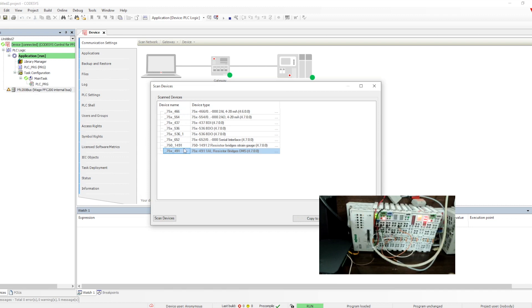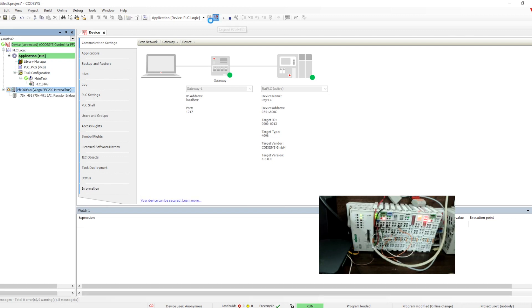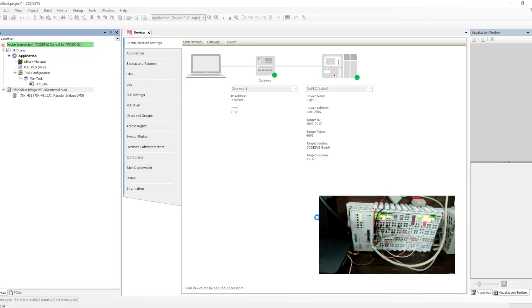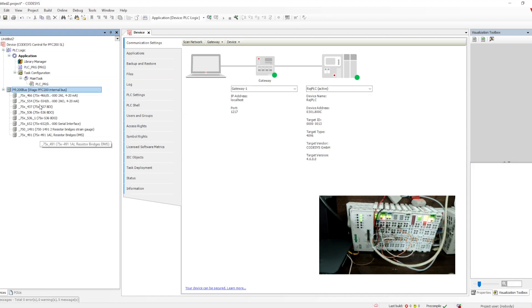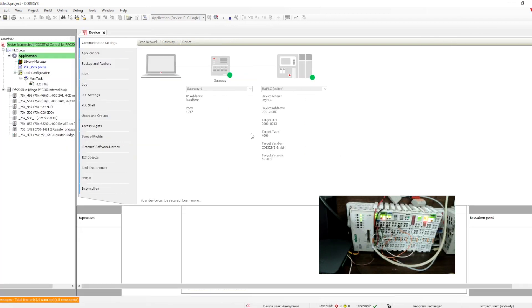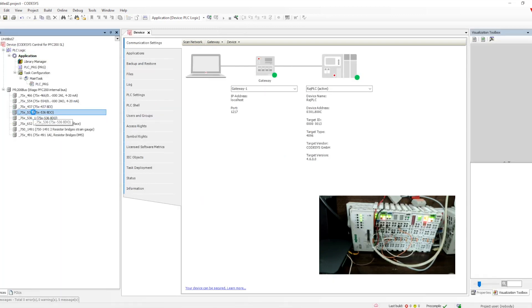We can right-click and scan the IOs, then copy them to the project. It copies all the IOs to the project. Now we can go offline and download again. Once we download again it will go to stop mode, and when we click Run, all the IO modules that are connected will become healthy and start communicating — meaning all IO modules will be scanned and shown here.